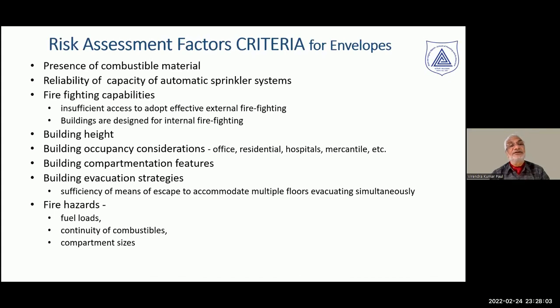Looking at risk assessment towards the end of this discussion, the criteria for development include: presence of combustible materials, reliability of automatic sprinklers, fire-fighting capabilities, height, occupancy considerations such as sleeping occupancy, compartmentation which can restrict the spread of fire inside and allow safe evacuation, evacuation strategies, and fire loads inside. Using these criteria, we can assess the risk a typical building poses, which can help us think about building envelopes in a more objective manner rather than simply from the point of view of thermal performance.